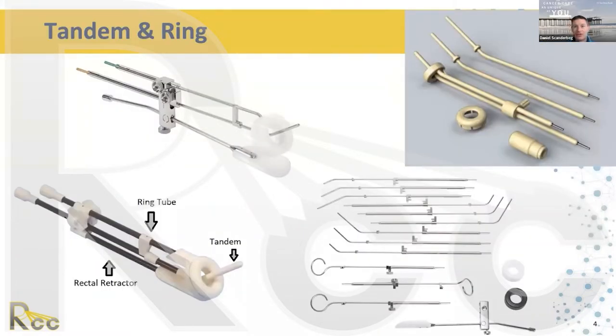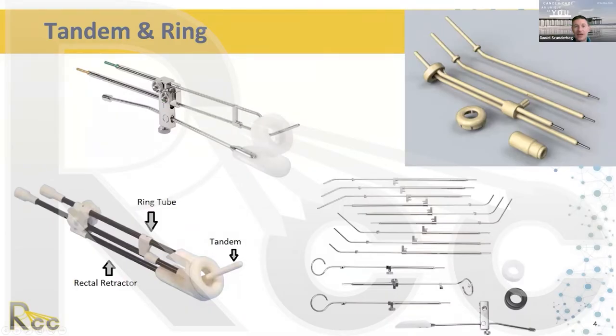Here are a few different types of tandem and ring applicators. They're all very similar in their overall design with the intrauterine tube — the tandem — and the ring, which is actually two rings in a sense for most applicators. You have the ring that contains the source path, and then usually there's a plastic ring or cap that snaps on top. Sometimes applicators have two different size caps. Most kits also have a rectal retractor, which helps dosimetry by pushing the rectum further posterior, increasing the space between the source and the rectum and helping spare excess dose.